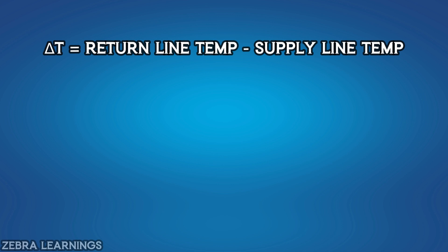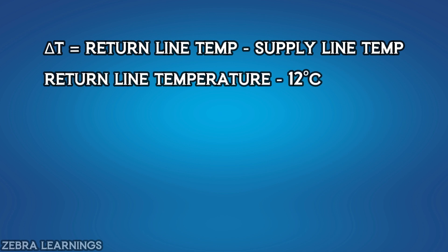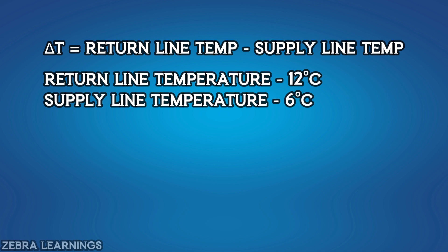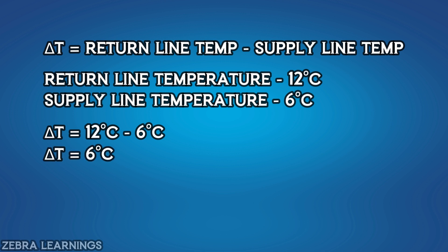To find delta T, we calculate the difference between return line temperature and supply line temperature. For example, if the return line temperature is 12 degrees Celsius and the supply line temperature is 6 degrees Celsius, the delta T difference is 12 minus 6, which equals 6 degrees Celsius. However, if you want to convert this reading to Fahrenheit, you should not simply convert the delta T answer to Fahrenheit. You should convert both the return and supply temperatures to Fahrenheit individually, and then calculate the difference.